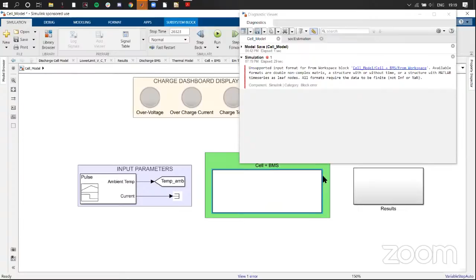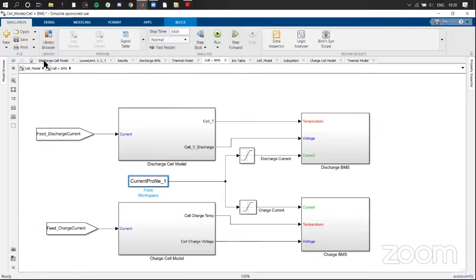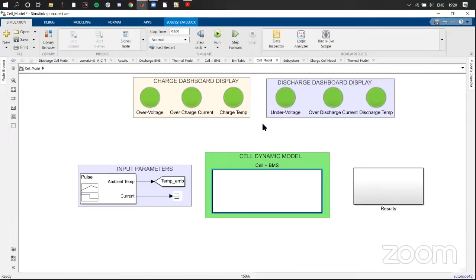This gives an overview of how we could model things. This model consists of a cell model and also a BMS model, and putting both together we can run the model and predict the state of the system for over voltage and under voltage. You can see on screen that for this specific current profile there was no error situation—no overcharge, over temperature, under voltage, over discharge current, or discharge temperature issues. This is a fundamental way of checking it.